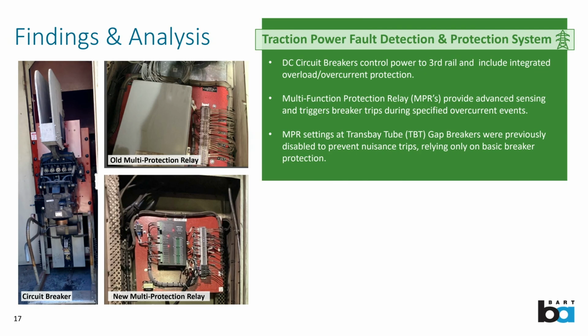Review of the records revealed that typically the DC breakers all have an ability to trip without an MPR. The MPR is a multi-function relay device that helps customize some settings - an additional layer of protection. Based on the review, these functions had been disabled during the time of the incidents. That doesn't mean the breakers didn't have the ability to trip, because they do have a trip mechanism, but it's more basic, and it would have relied on that basic mechanism.